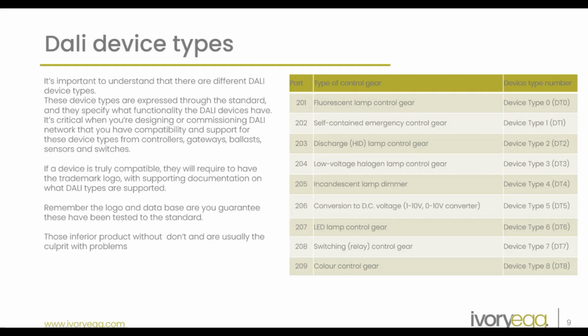If a device is truly compatible, then it's required to have the Dali trademark logo with supporting documentation on what Dali types are supported. Remember, the logo and the database are your guarantee that they have been tested to that standard. Those inferior products without them usually are the culprit with all the problems.